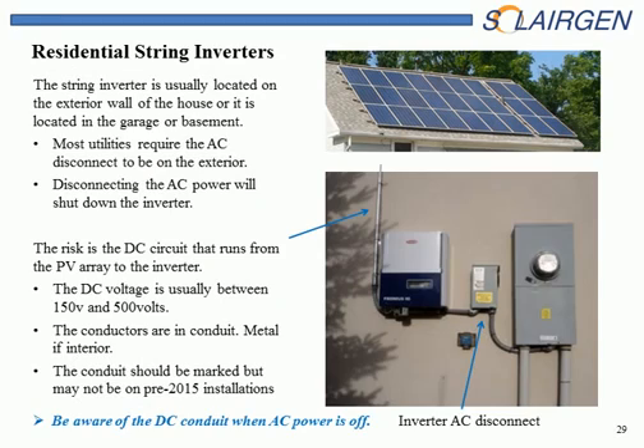Here we have a string inverter, a residential string inverter. You can turn this AC disconnect off or pull this meter and it will shut down the AC power. But if it doesn't have voltage safe optimizers on these PV modules, then you have high voltage DC running from the PV array down to the inverter. So be aware of this conduit. There is high voltage DC in it, unless it's marked otherwise.